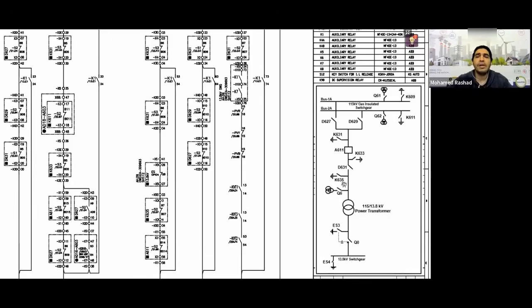All right. Regarding the ground here, which is case 635, what does the ground look at? It looks at the switches. Okay, the switch before it, 631, is open. 631 is open. All right. Is there a switch after it? Yes, there is a switch after it. It's not a disconnector, it's a breaker and ground. Didn't we agree that the breaker is at 13.8 kilovolts?